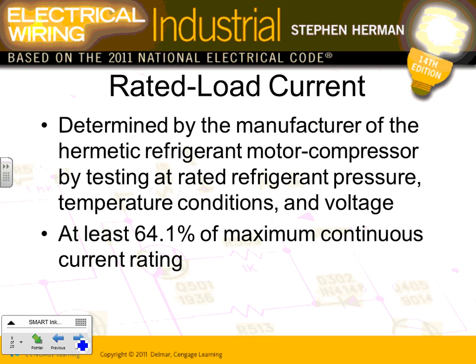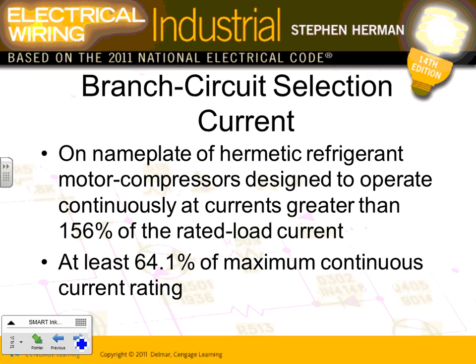Rated load amps have to be on the nameplate, and it's typically 64.1% of the maximum continuous current. You don't have to know that, but it is 64.1%. And it's also on the nameplate, like we said. Then branch circuit selection current: the manufacturers give you either rated load amps or branch circuit selection current, whichever, and you're supposed to use it. Same thing, it's very similar, and it's equivalent to 64.1% of maximum continuous current.